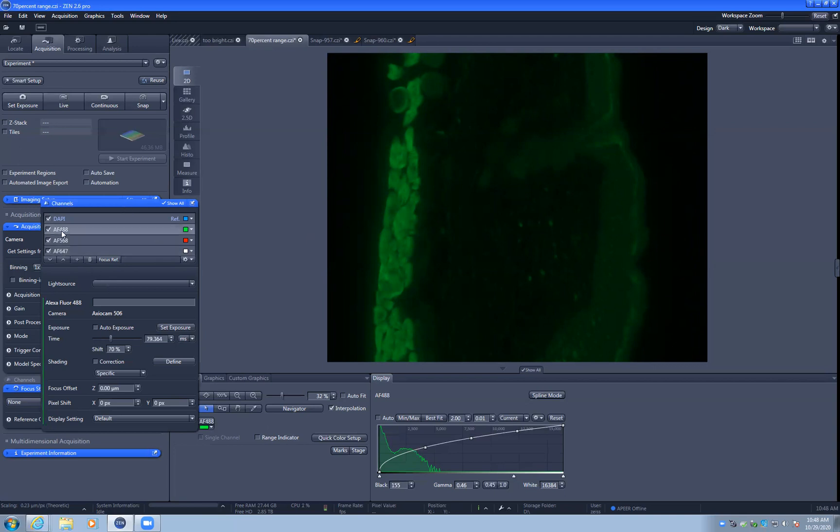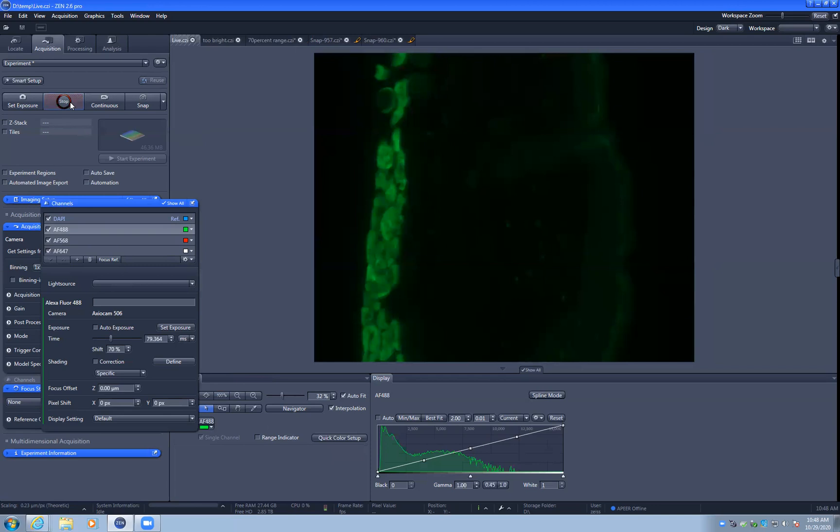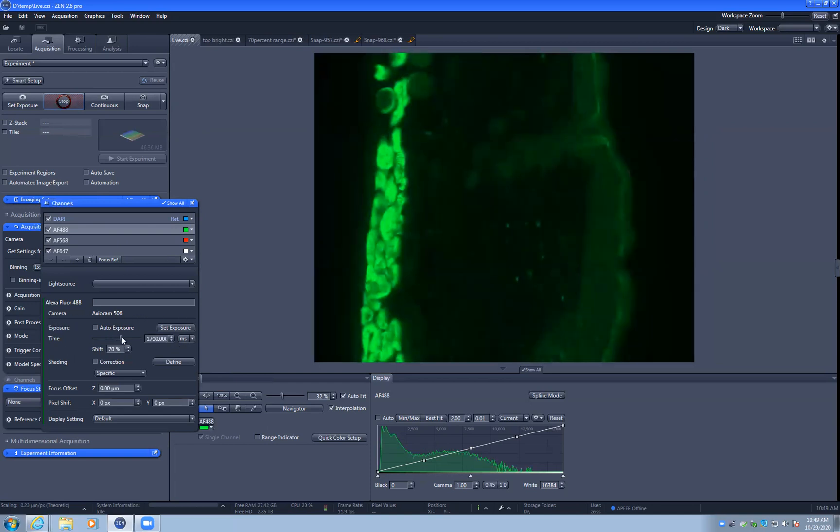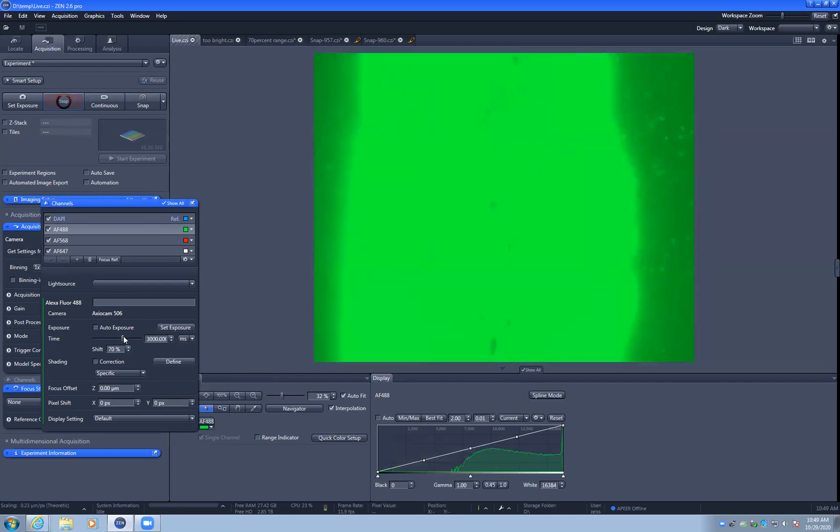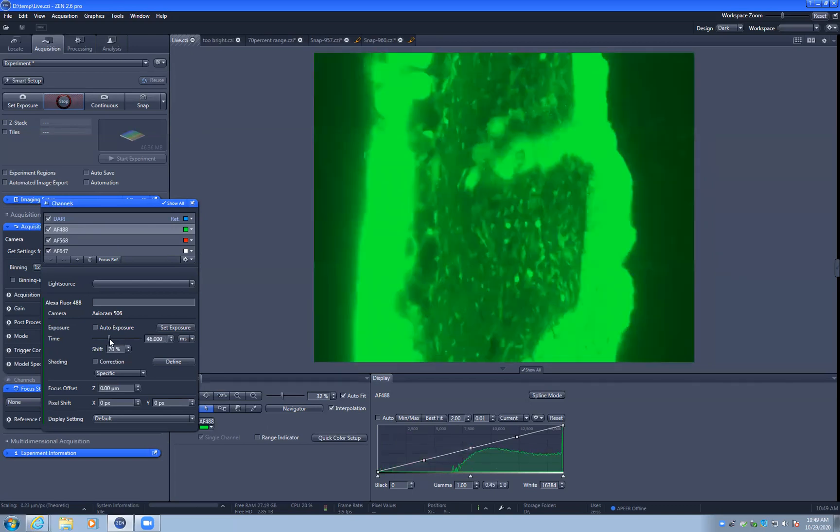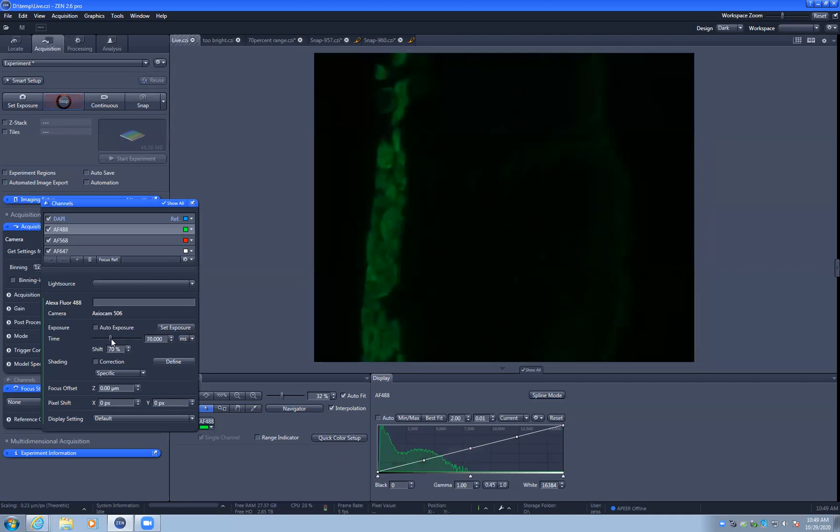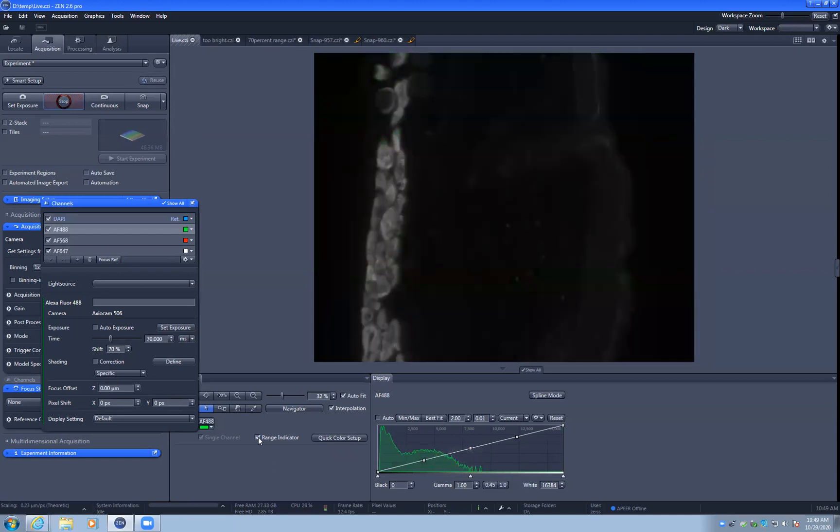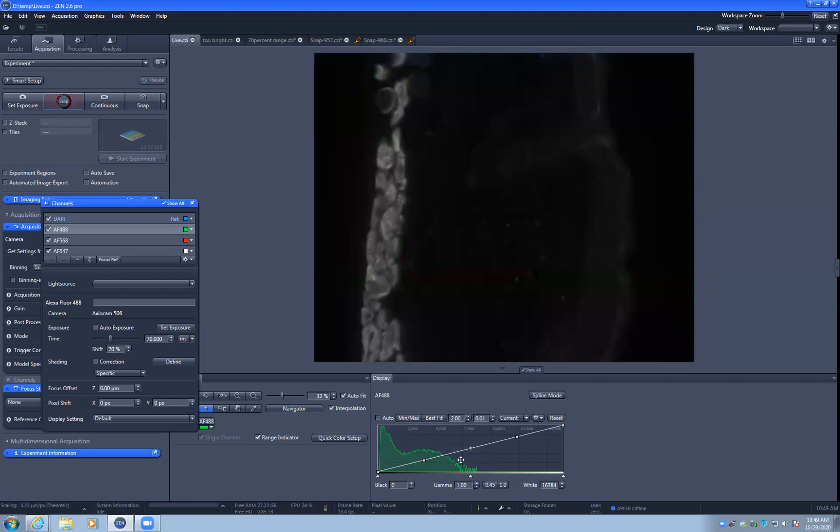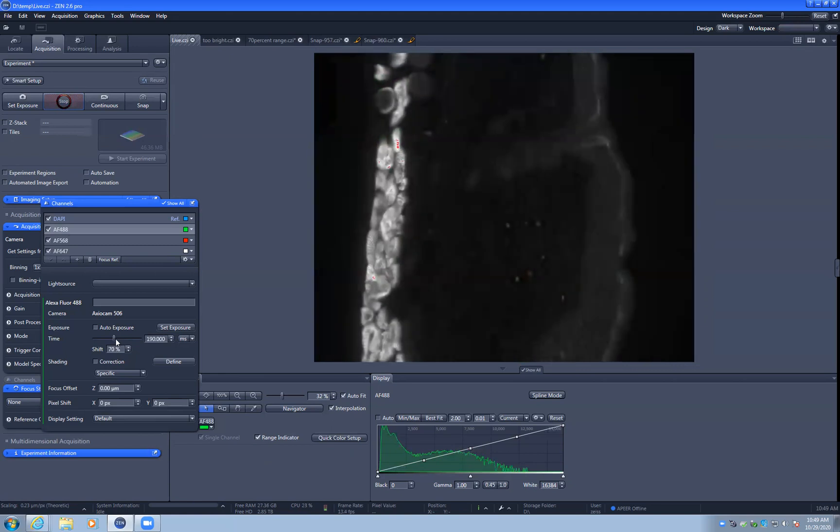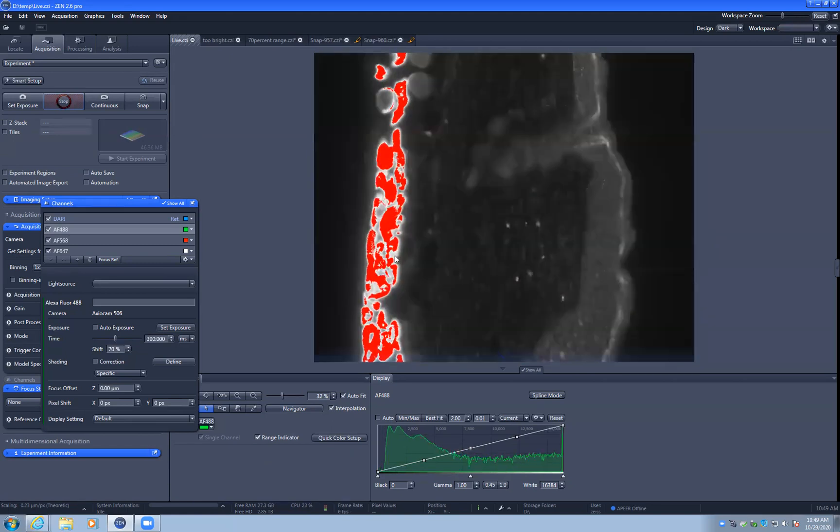Let's look at just the green channel. So I clicked on green AF488. And if we go live, we have a live image. And we can manually change the exposure time. We can bring it up. Now we're saturated. And we can bring it down. And we have a tool that shows us when we saturate our pixels, which is this range indicator button. So when I click on the range indicator, you can clearly see that this is not saturated. We're in the green zone. And if we look at the histogram from the lookup table on the bottom, you can see we're using about 50% of our dynamic range. If I make the exposure time longer, you can see now we have saturation. The pixels shown to us as red are saturated, you can see this peak at the far right.